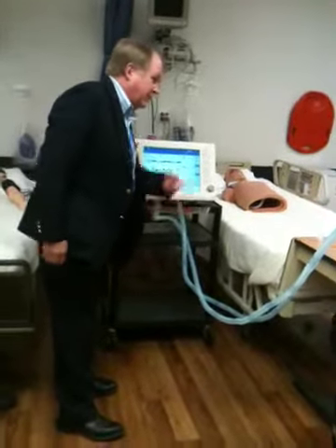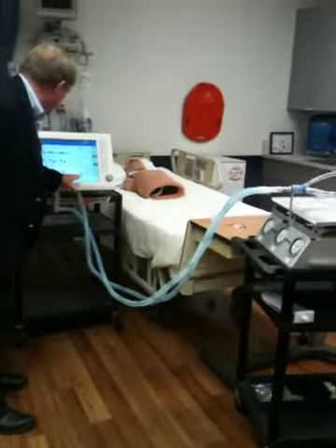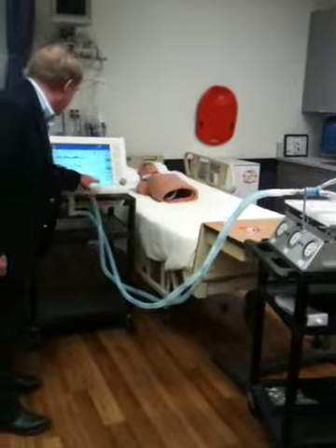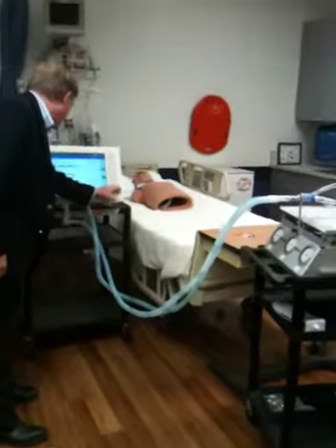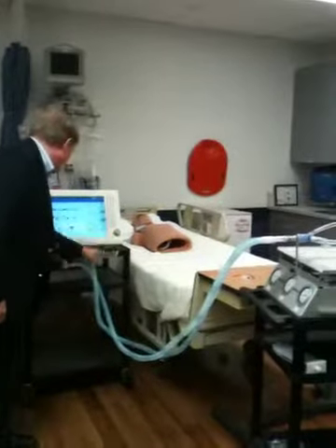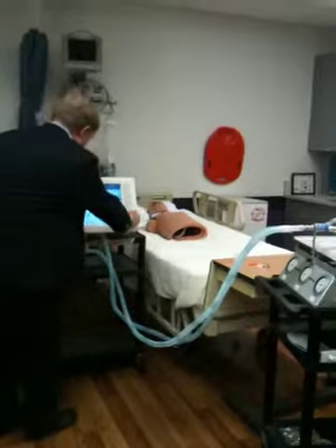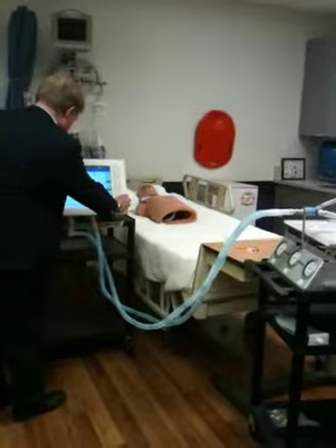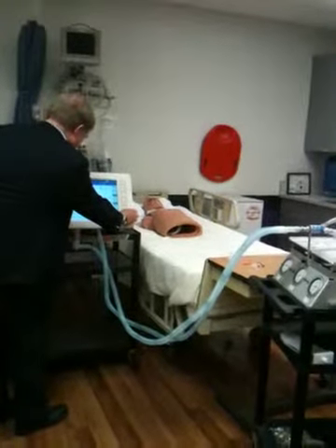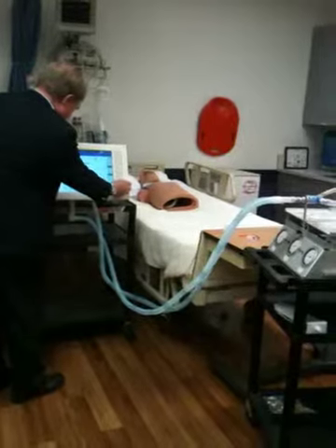Now, this lung does not do the same as a human lung would do, in that it keeps a constant compliance throughout the entire cycle. But if I look at it right in here, my static compliance is 32.9. If I come up, it drops. And so I want it to be above the drop.